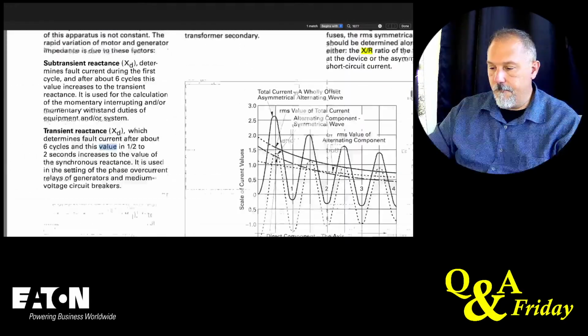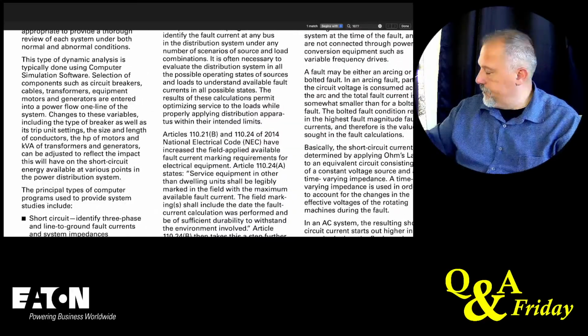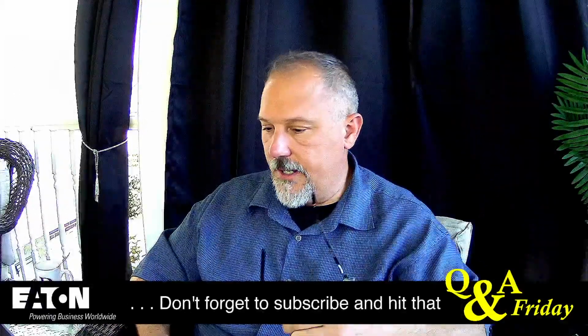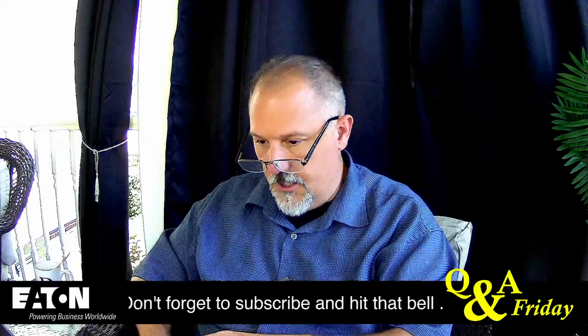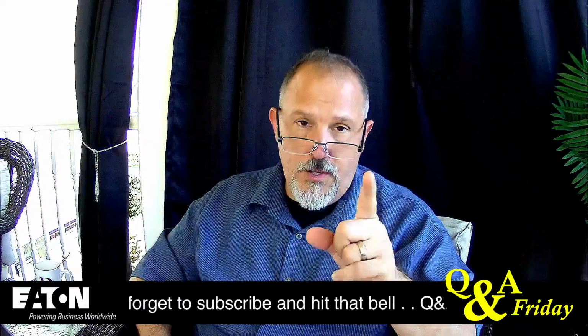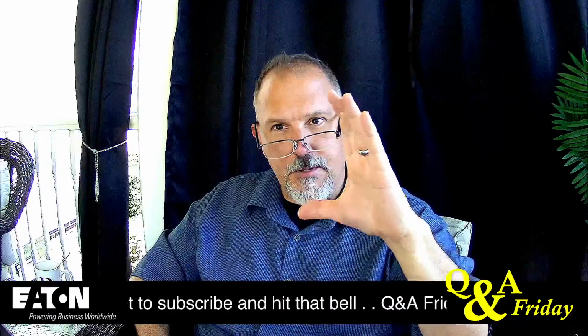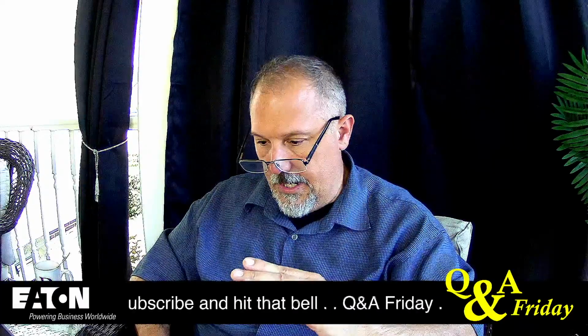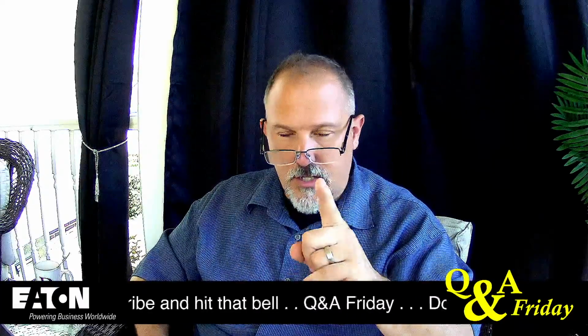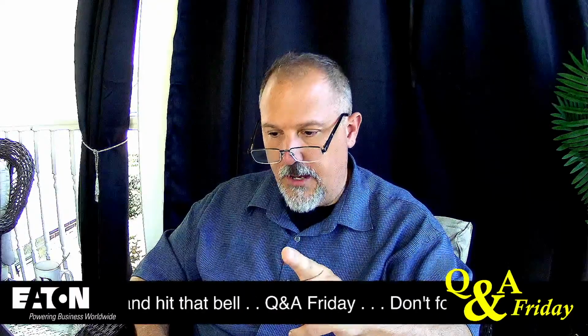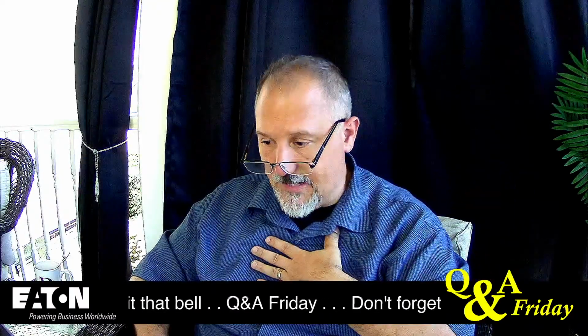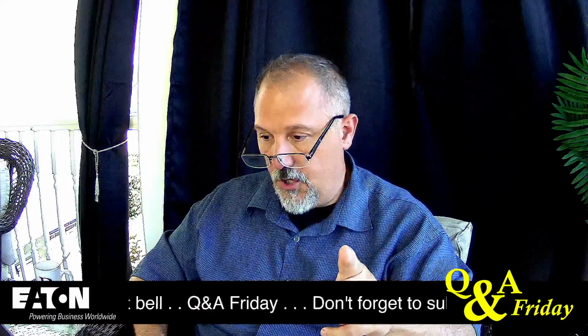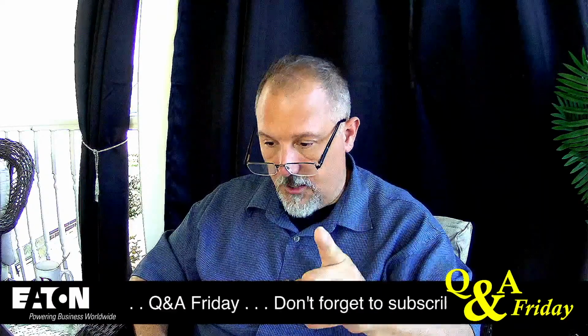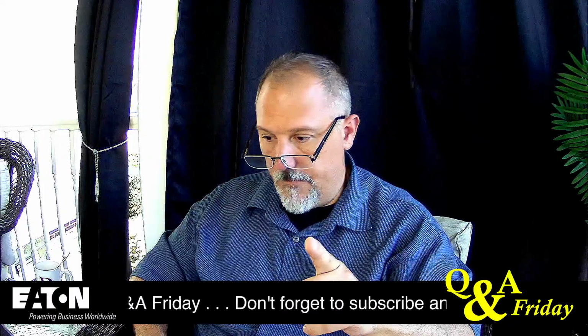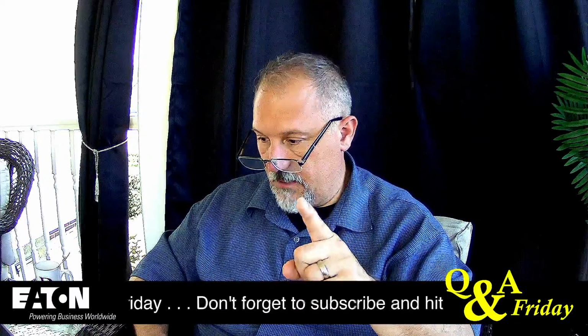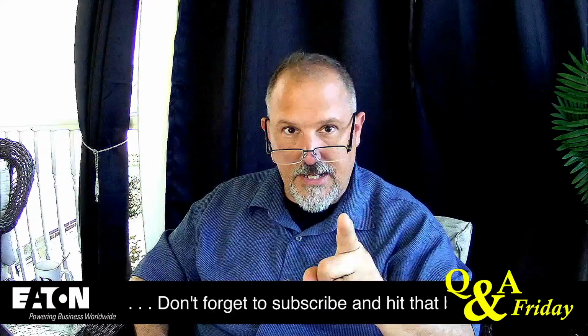Where are my values? Give me a second. I've got to find the value here. Because what we do is we assume an X to R ratio value that establishes a peak value with a slope. And if your X to R ratio is different than, or outside of, the extremes of how we've tested it, then you need to adjust the interrupting rating of the overcurrent protective device. That's an important piece of the pie.